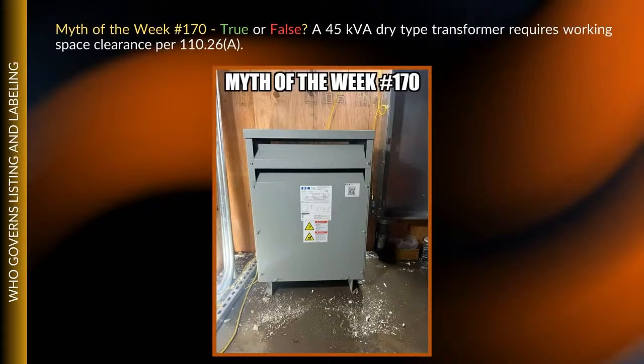So here we have a 45 kVA dry type transformer. It says requires working space clearance per 110.26A. That is absolutely false. There is no reason that you need working clearance on this because it's not likely to be worked on while energized. I could see in some facilities if they have a periodic maintenance spec or something, but this is the NEC discussion, not what DuPont does or what Phillips 66 does. A lot of people try to twist that and say the job spec will say that. Well, that's fine, but it doesn't say it in the NEC.